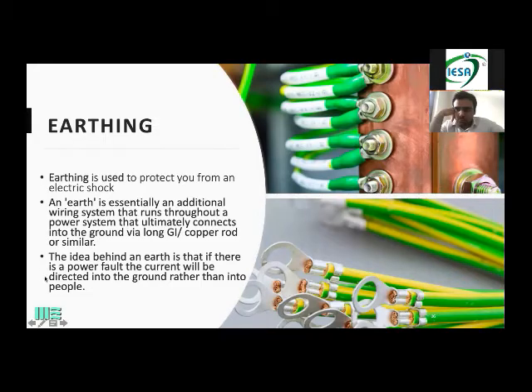So the idea behind an earth is that if there is any power fault, the current will be directed into the ground rather than into the people. What does that mean? There are 2 types of earths which need to be done always on site. When you're using a genset, there is a neutral earth and then there is a body earth. These 2 earthings always need to be done separately for each and every genset. If you have 40 gensets on site, every genset needs to have a neutral earth. The body earth you can loop.